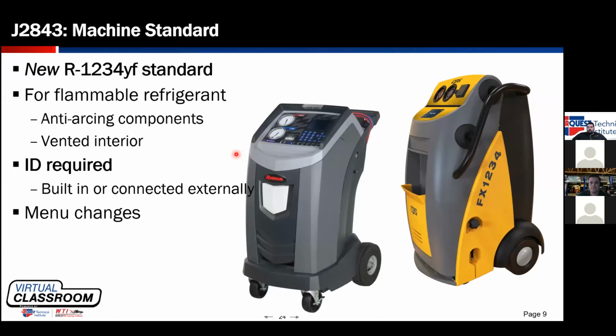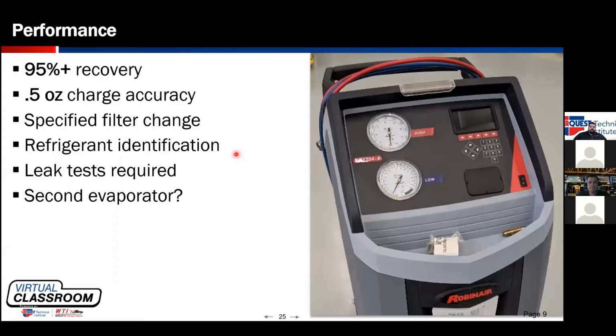There are also some menu changes, things like we're picking if the machine is, or if we're working on a hybrid or a non-hybrid vehicle. Before we recharge, the machine is going to require you to do a gross vacuum decay leak test, and you're also going to do an evaporator leak test. And we'll talk about some more as we go along here as we get into leak detection. So the performance of the machine for 1234YF is very, very similar to the standard for 134A, the J2788 standard. What that means is we have to recover 95% of the refrigerant in the system within a half of an hour. When we recharge, the charge has to be accurate within a half of an ounce.